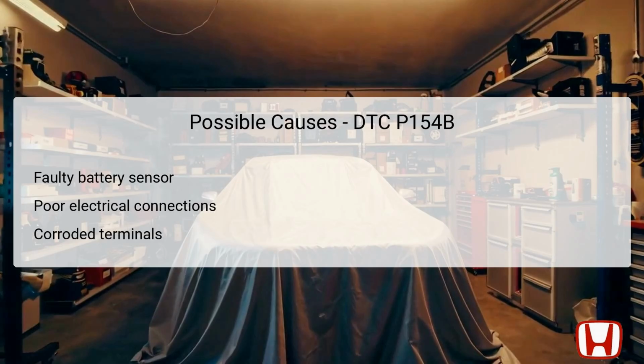Corroded terminals, often overlooked, are another significant point of failure. Corrosion can impede the electrical flow, leading to erroneous readings. Furthermore, the sensor's mounting bracket or location might also lead to issues if it's not properly secured, thus affecting its ability to provide reliable readings. Understanding these causes can guide technicians in effectively diagnosing the problem.